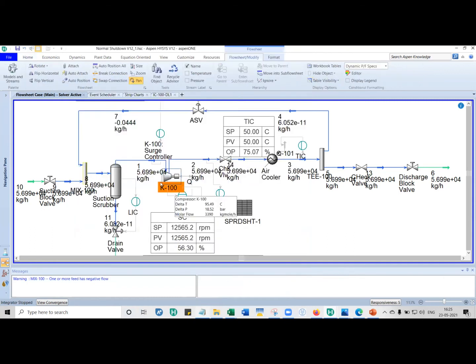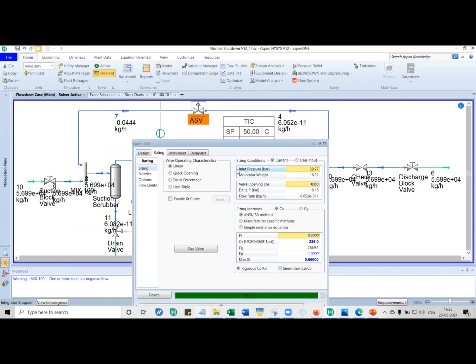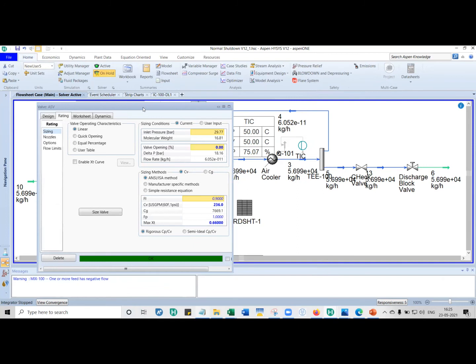For the gas compressor you have to have your performance maps. For the ASV — the anti-surge valve — when you're sizing it, remember it is the vendor who decides what the ASV size should be. But if you're in the proposal stage or front-end stage where the manufacturer hasn't yet given you data, you can estimate the CV tentatively. However, you must share those results with the compressor vendor, because he gives the guarantee and warranty and has the final say on what the anti-surge valve size should be.